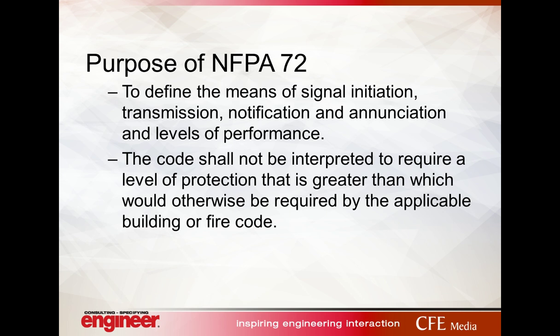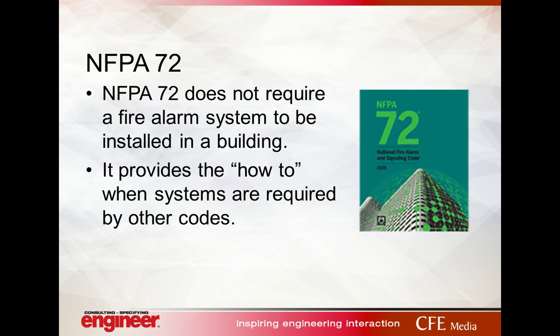The primary purpose of NFPA 72 is to address the manner in which the system performs, how it transmits signals, and how notification is placed so that occupants and emergency responders are appropriately notified. It addresses annunciation and levels of performance. NFPA 72 works in tandem with the building codes, and we are seeing more specific requirements being placed in building codes relative to fire alarm. In cases of conflicting requirements, the building code adopted in the jurisdiction generally takes precedence. So NFPA 72 provides the how-to when other building codes require a fire alarm system.